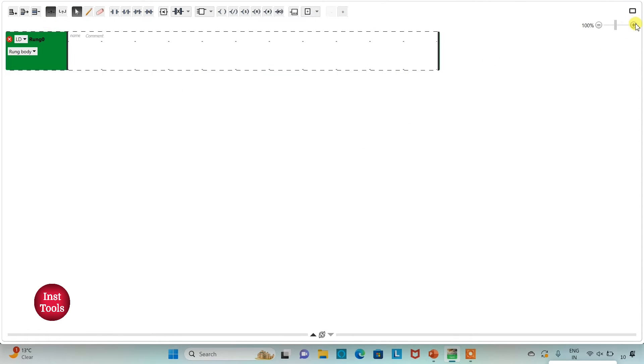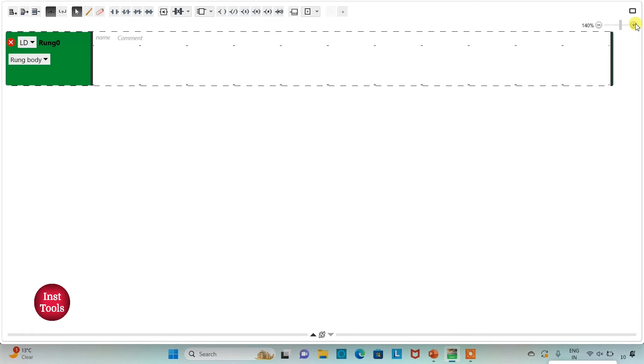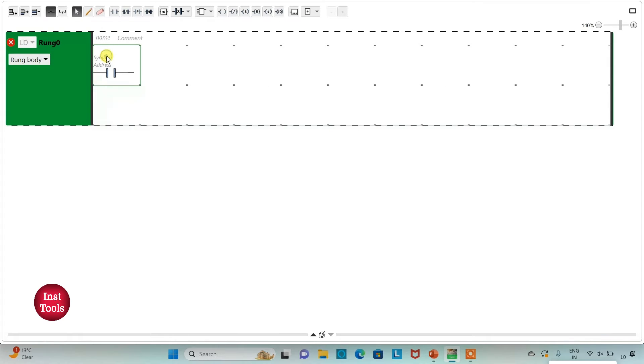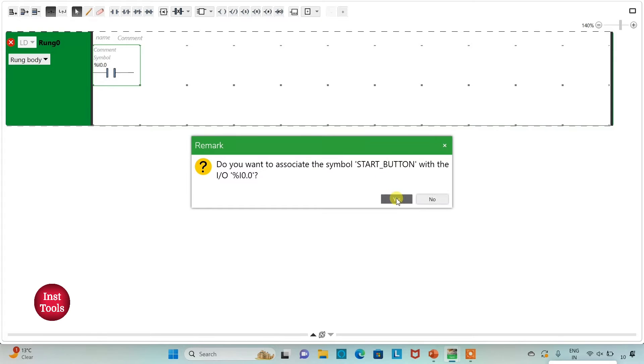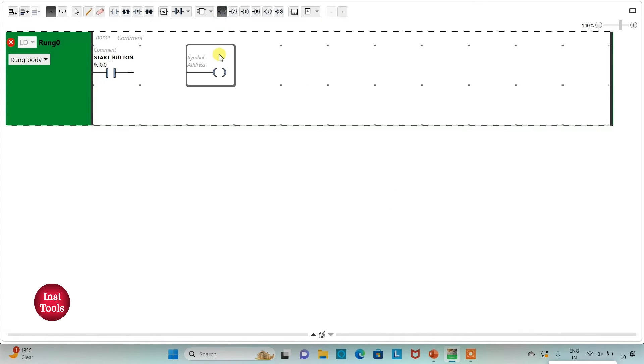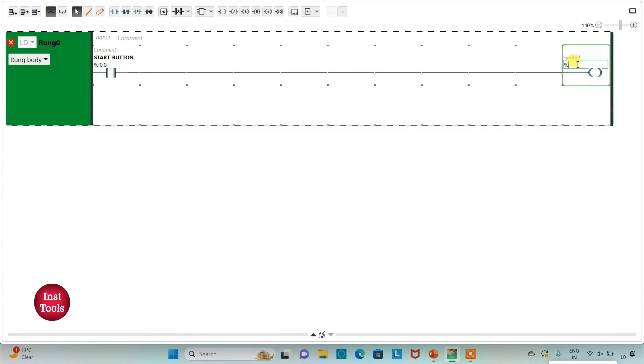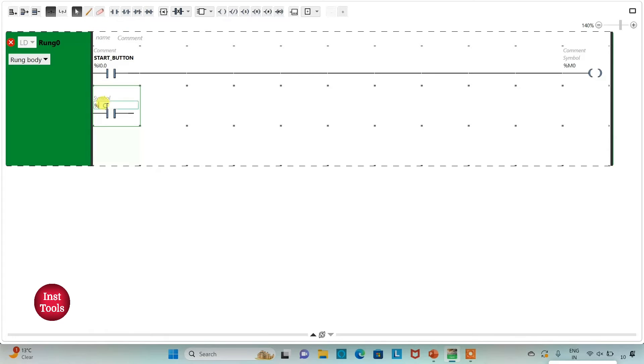I will click on full screen mode and zoom in. First I will insert a normally open contact and assign the address I0.0 with the symbol 'Start Button'. Then I will insert a coil and assign the address M0, which is a memory bit, and draw a line to connect it.